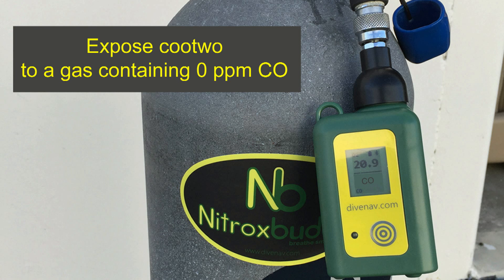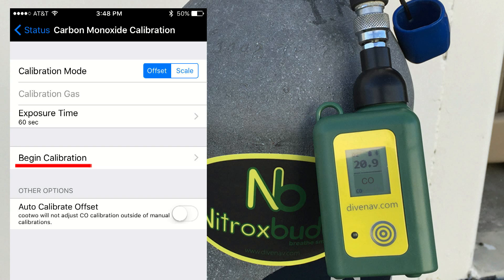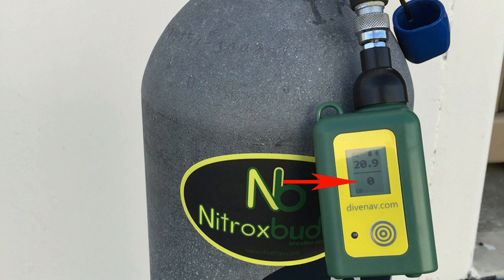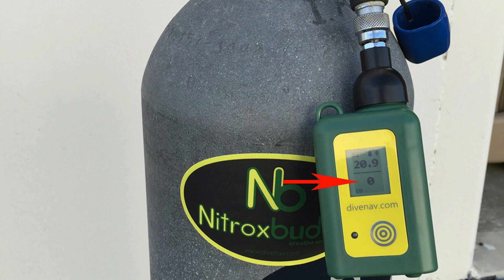Now expose Q2 to a calibration gas containing zero ppm carbon monoxide and then tap on Begin Calibration. When a carbon monoxide calibration is in progress, Q2 will display CO and the reference gas value alternating on the bottom part of the display.